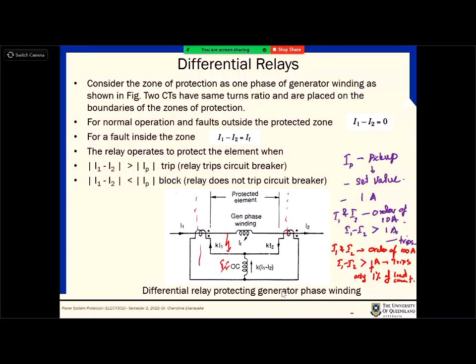If there is any fault inside this zone, there is a fault current IF, which is going through this center branch. The relay will only operate if the magnitude of that difference is larger than the pickup value. If it is less than the pickup value, it blocks. We are the ones who set that IP. We say that IP is this value. That depends on a lot of other conditions, such as the magnitudes of the currents you are working with and the typical leakage current. A lot of other things will define this IP value.